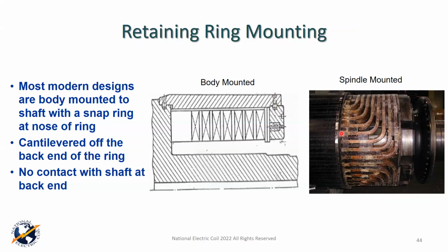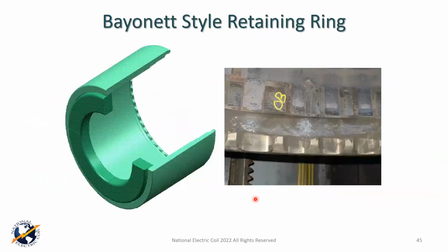And there are modifications you can put on these rotors. You can even put in dead turns on some of them with a beryllium copper on the top. There are things that you can do, but you need to realize that these spindle mounted machines are susceptible to top turn cracking, and it should be easy for you to find the information in the bulletins from GE and others on it. So that's kind of what we wanted to do there.